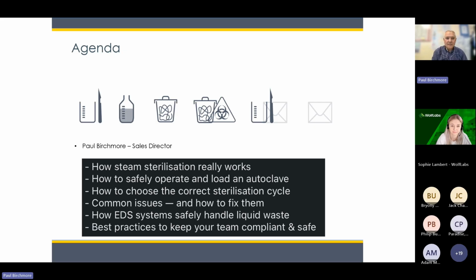So my section will be about 30 minutes, running through, as it says on the screen there, those points: how steam sterilization works, how to carefully and safely load and operate an autoclave, choosing the correct cycles, some common issues, which we'll hopefully cover as we go through all of these points, best practices, and how to keep you and your staff safe. And then finally, right at the end, a new acronym for you, EDS, Effluent Decontamination System. It's a relatively new idea, but it's specific to sterilization of contaminated liquids, which I'll touch on in more detail shortly. So without further ado then, let's get started.